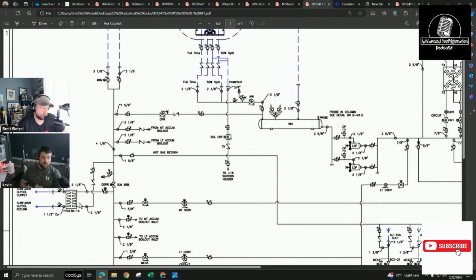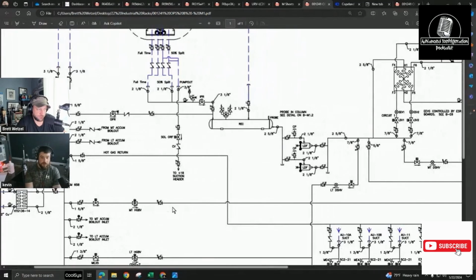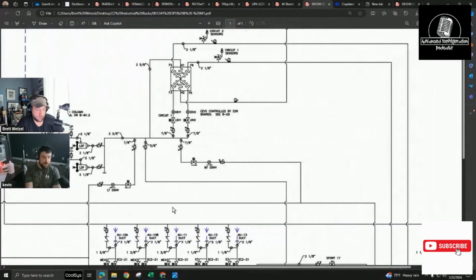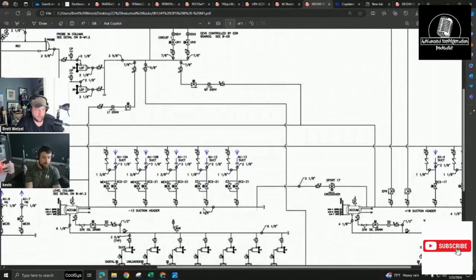I see that disconnected on a lot of stuff, and that plays hell on your head pressures. Heat reclaim tanks don't increase your head pressure, they reduce it. Mm-hmm. Especially if you've got a decent load on there, you're taking away a lot of superheat, and that condenser coil is doing more. So you want to be able to have that heat reclaim running, and don't let anybody tell you that heat reclaim is a bad thing.